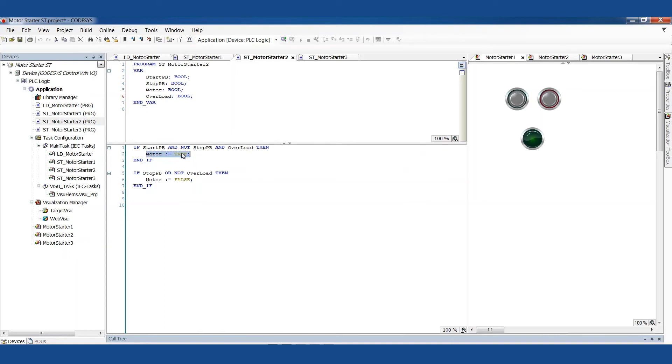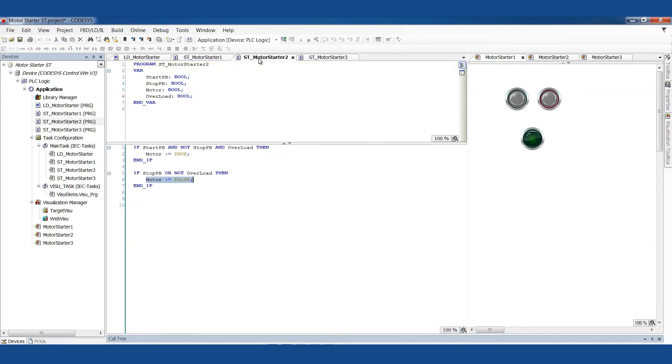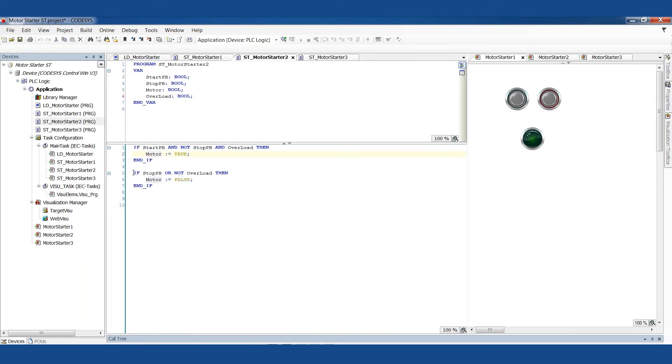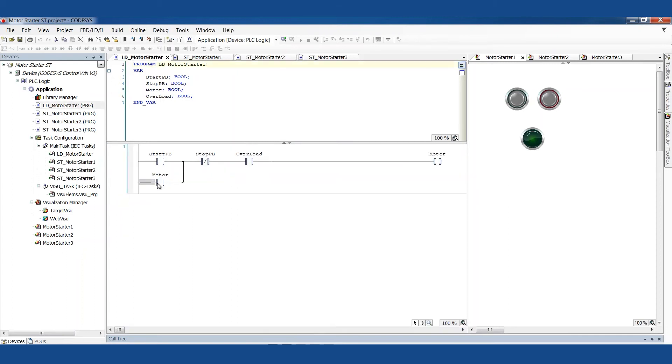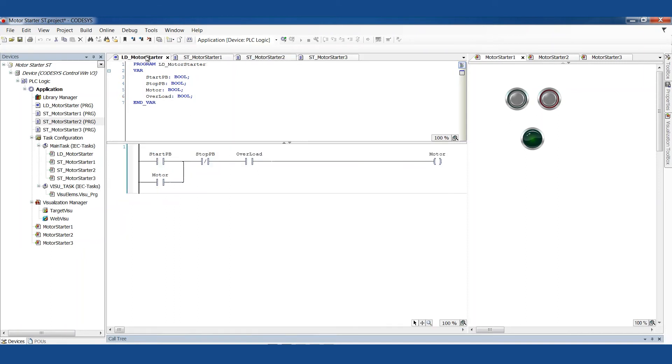What is the condition where I want the motor to be true? And what is the condition where I want motor to be false? Again, this is on and off. It's the same thing. Because I'm saying if these specific conditions do this, and if these specific conditions do this, this doesn't have the latching function like this. It's not self-latching. It only writes in the condition where it wants to change the state. But this variable will keep whatever state we last wrote to it. So it's sort of self-latching. And you might think about it in ladder logic like a latch coil and an unlatch coil instead of a regular coil like this.